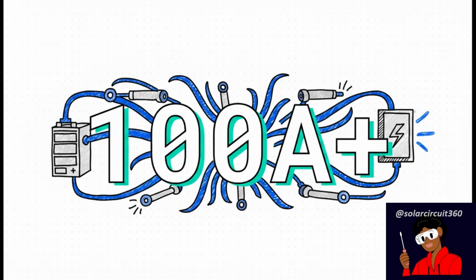Over 100 amps. Under heavy load conditions, a 5 kilowatt inverter on a 48-volt system can easily, and I mean easily, draw over 100 continuous amps of current. I really want you to stop and think about the sheer volume of that. That is a massive wave of continuous DC current, constantly squeezing through every single cable, every lug, and every tiny connection point in your system.